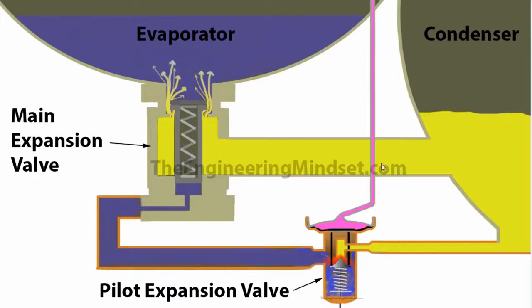When the bulb detects the maximum allowable superheat, it's at full pressure now. The refrigerant inside is fully expanded, and that's pushed down the pin rods inside the expansion valve all the way down. The maximum amount of refrigerant from the condenser is now flowing through the line and has pushed the piston body completely off its seat, and that is allowing the maximum amount of refrigerant to flow into the evaporator from the condenser.